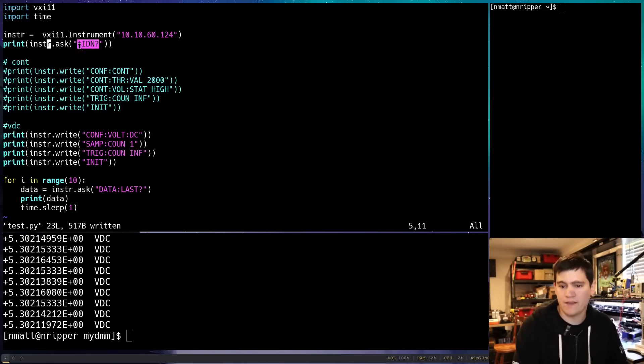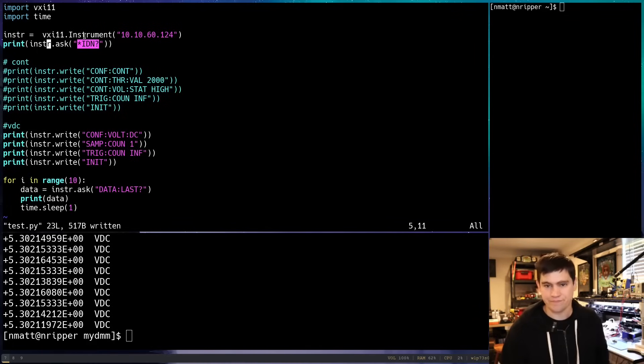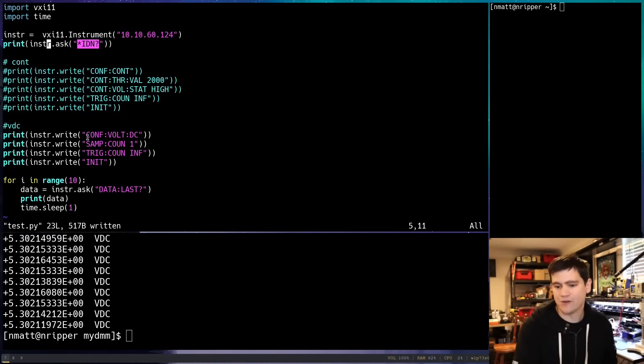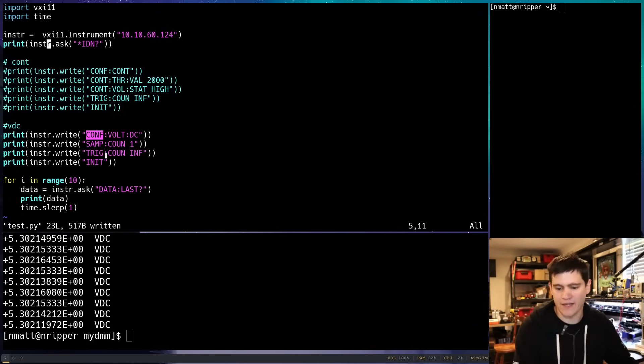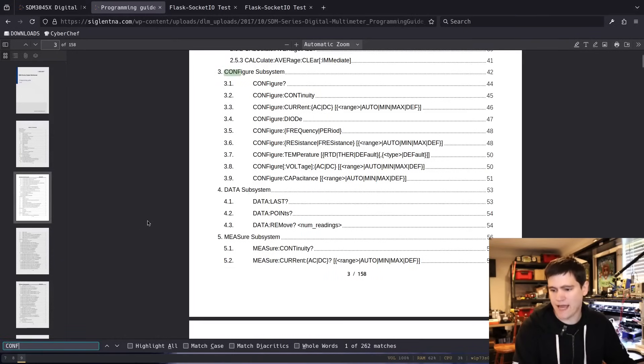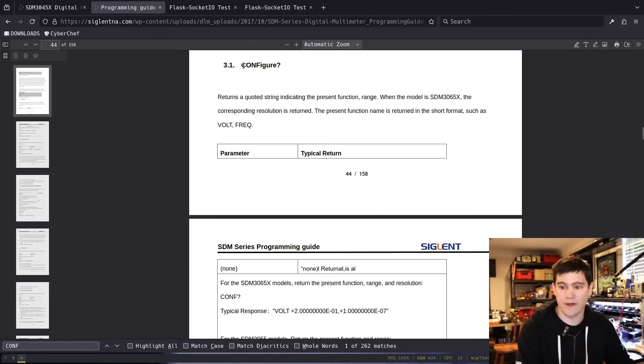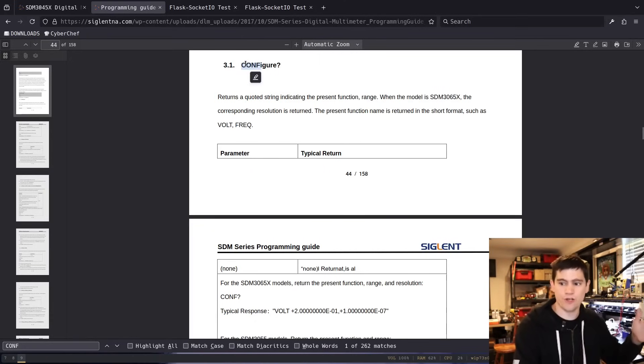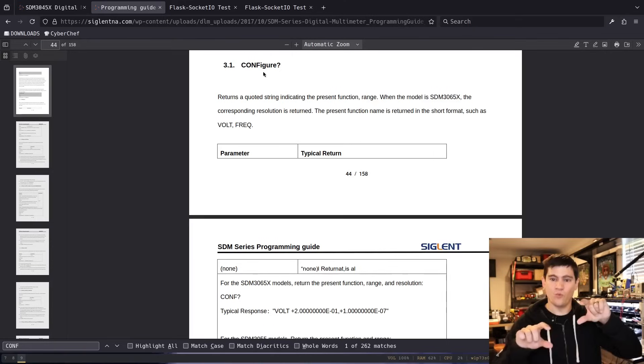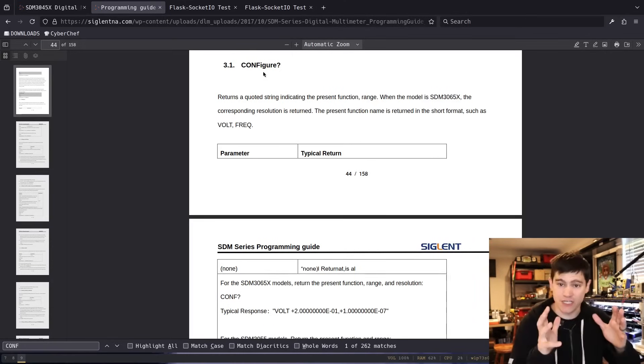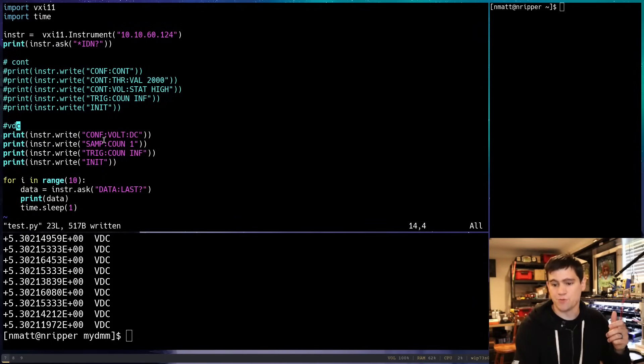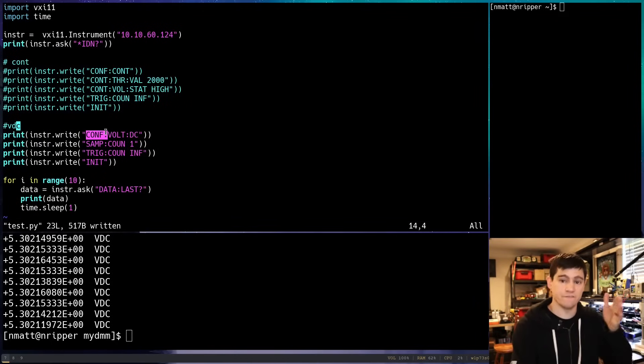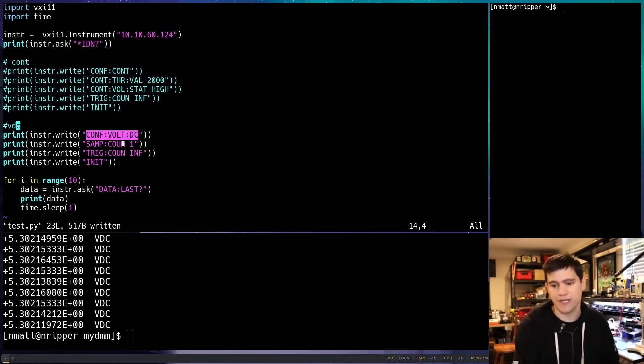You'll notice that some of these commands have a question mark at the end. In this command language, a question mark means that we expect a value to be returned to us. Whereas, these other commands are more just like you're just writing a configuration, and you don't expect a response back. The first command that pretty much everybody in every example tells you to run is this identify command. All these commands actually have shorthand format. You can see that the configure command, you can just type CONF, or you can type configure with the capitalization showing you where you can make the shortened version.